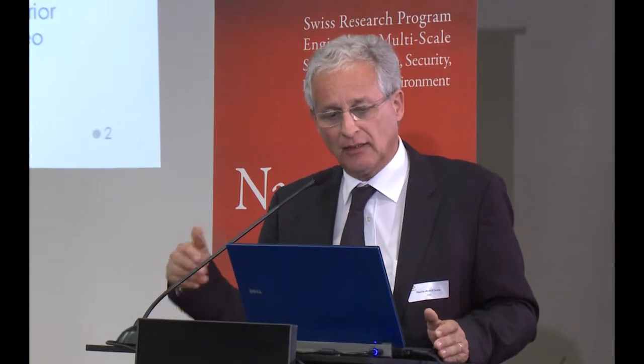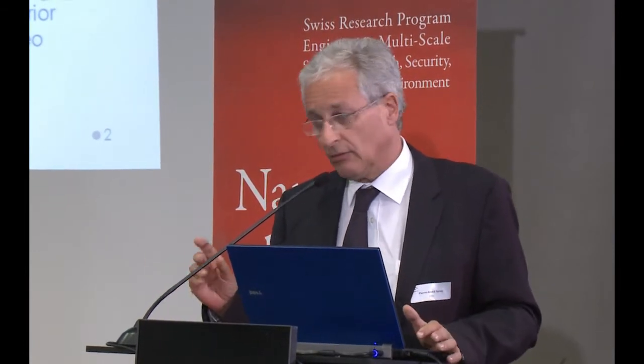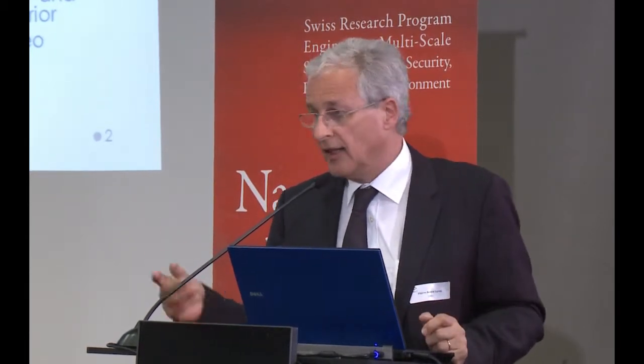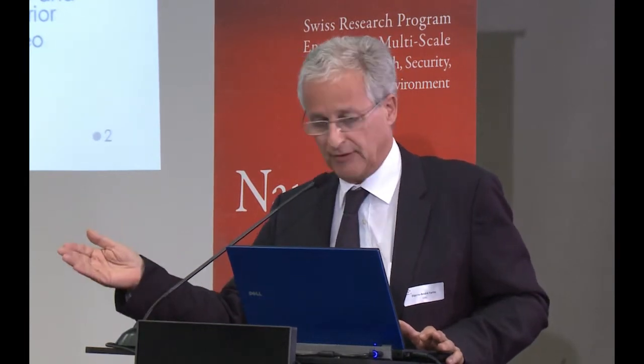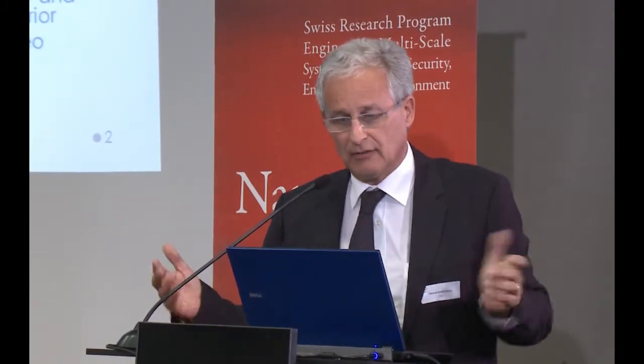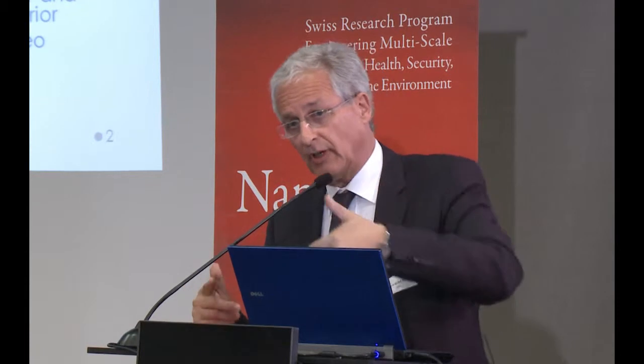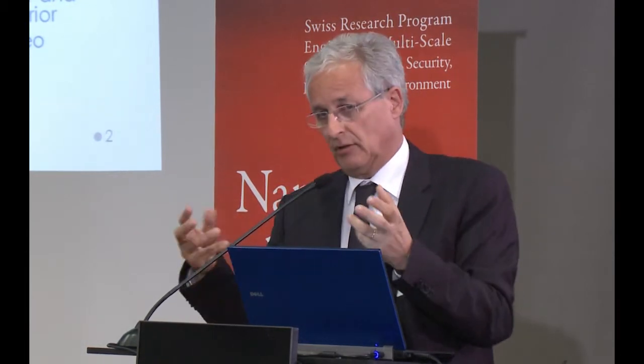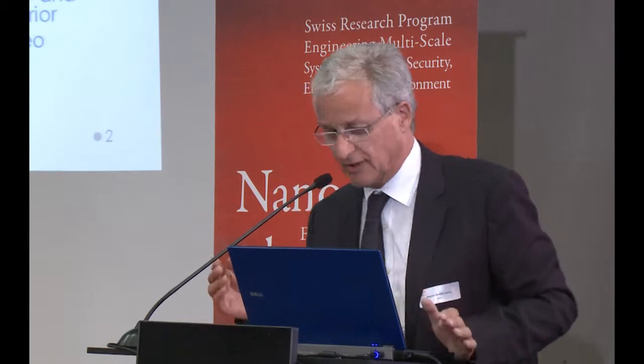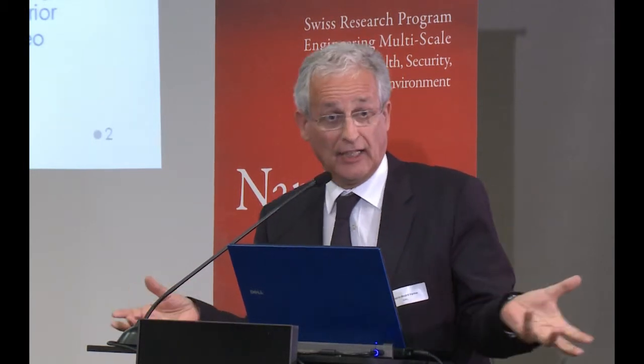The ECG chest band, in order to access the sensing, it's only 3 electrodes. And in this case, we would like to compute the heart rate, of course, and to compare the data together with the EEG. And in this case, the power budget is up to 1 milliwatt. And finally, we have a patient environment monitor, which is on the wrist. And it's a context sensing, and it's used because for young children or for elderly people with Alzheimer, it's not convenient to manipulate the data. It's quite random, the reaction of these people, and it's the reason why the physician would like to have a patient or environment monitor, something like a watch.